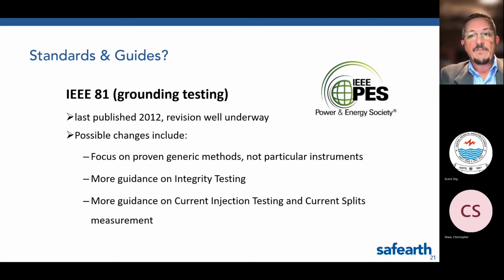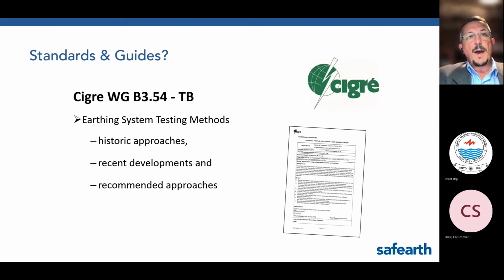IEEE 80 traditionally gave a lot of approximate guidance, and it's proven to be incredibly approximate in some cases. So measurement is turning into a very reliable way to tune your designs around what current distributions really will be. So expect in the next year or two a new edition of IEEE 81 with a lot of new guidance on effective, reliable emerging test methods. But there's another document coming out as well that you might want to have a look at too.